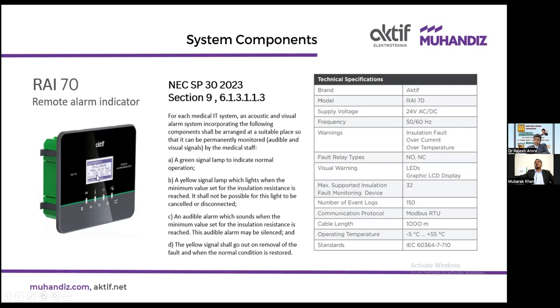As per the standard, we should have a green signal lamp to indicate normal operation, and a yellow signal lamp which lights when the minimum value set for the insulation resistance is reached. Means yellow light for alarm, green light for healthy, and an audible alarm which you can mute but cannot reset. When there is an alarm, it can be muted, but it should not be possible to reset unless the fault is cleared. So these are the requirements for this remote alarm panel.